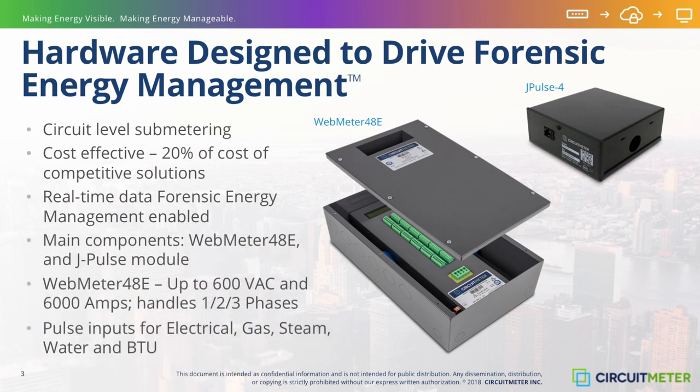In this slide, we present the primary components that make up the CircuitMeter hardware solution. The foundation of the system is the WebMeter 48, which provides monitoring for 48 circuits. The built-in voltage sensor is used in applications up to 600 volts and samples at over 200,000 hertz in order to generate the real-time electrical readings necessary for true RMS power calculations. The WebMeter 48 is self-powered, so no power outlets are required. If communication to the cloud is disrupted, the WebMeter 48 has up to 365 days of 15-minute interval data stored in onboard memory.